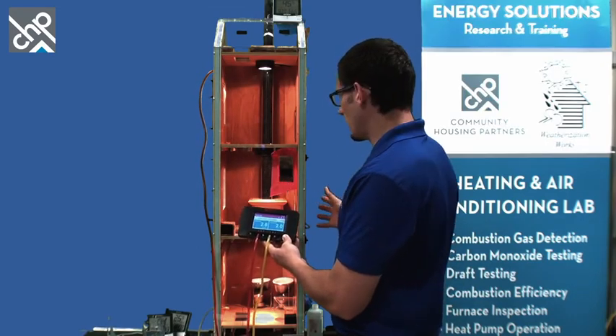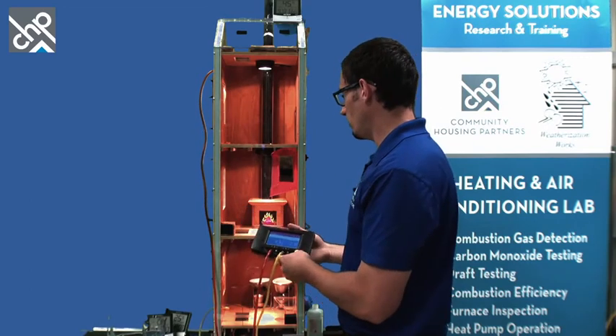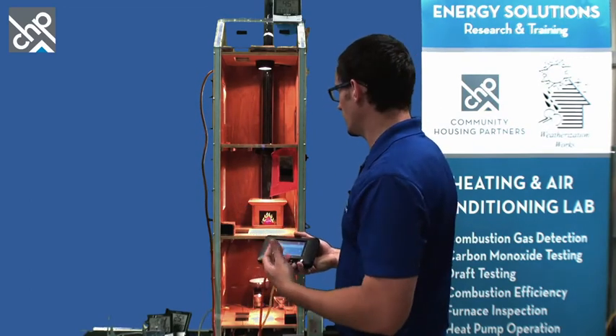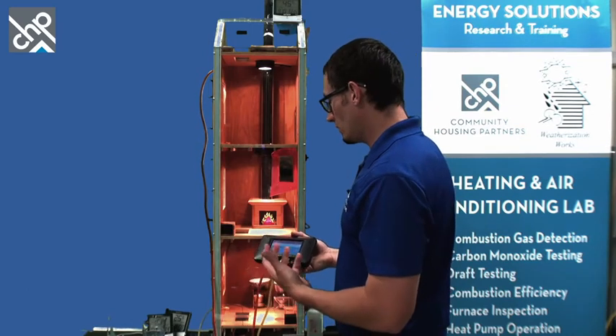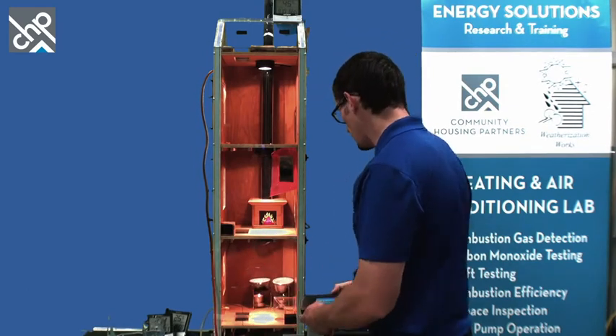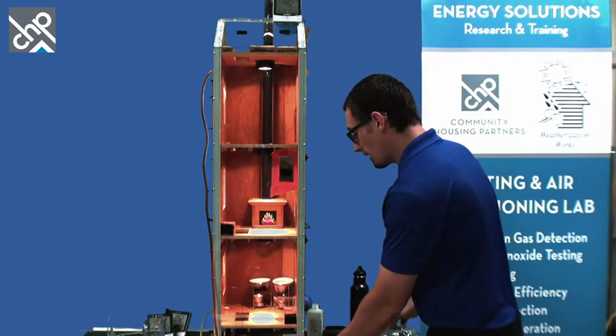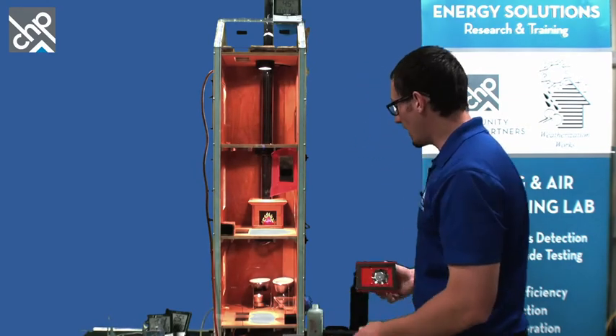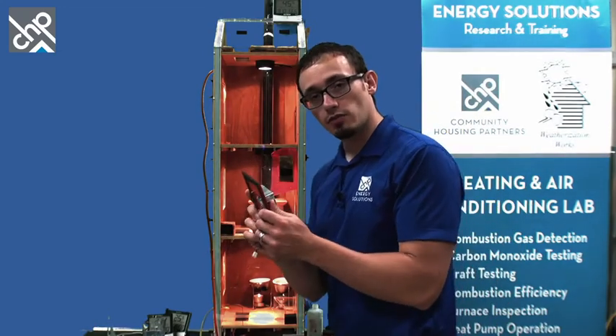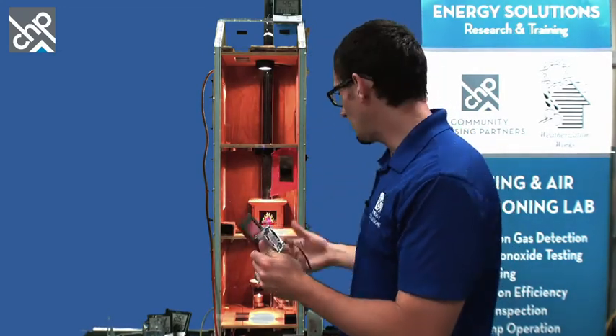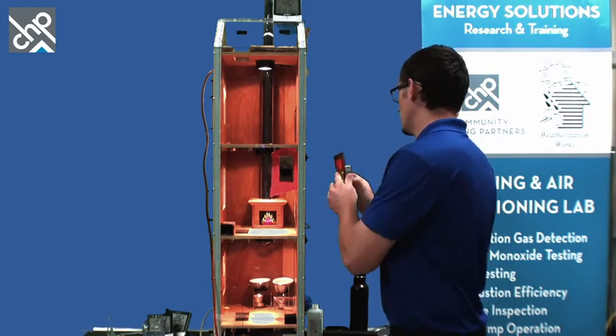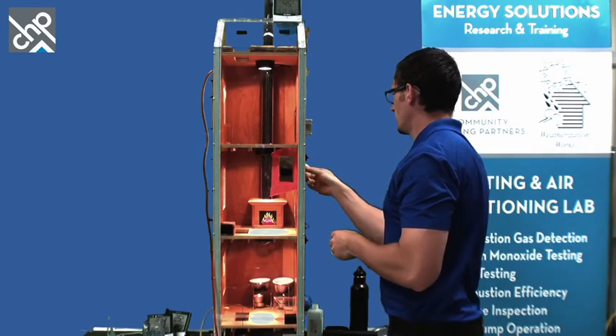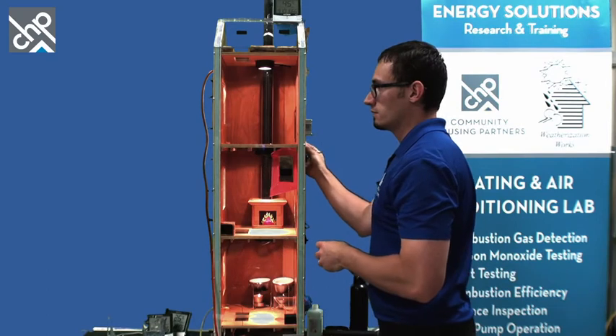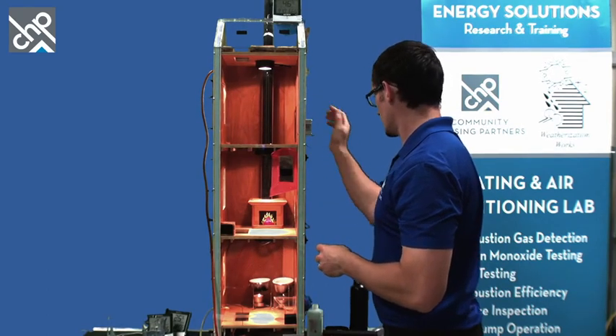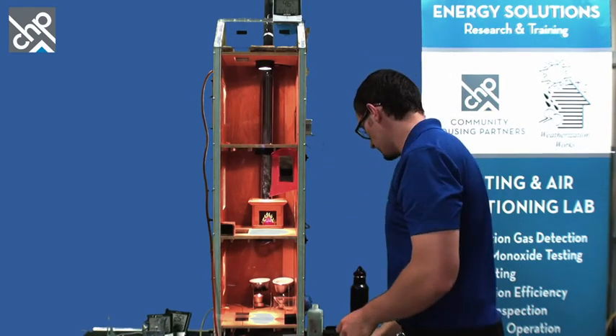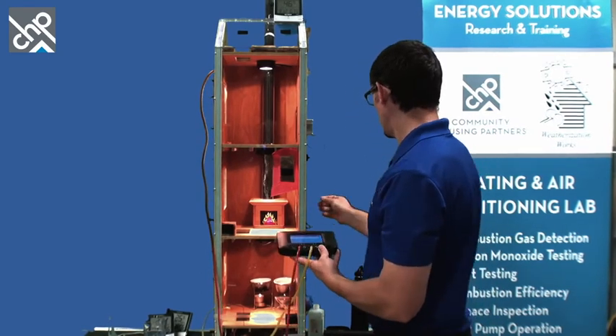So I can turn it around and I can do supply pressure, positively pressurize the building envelope. Or best case scenario, maybe I have two fans, or maybe I have an ERV, or maybe I have an HRV, some sort of balanced recovery. So I'm going to add another fan, exhaust fan to complement my other one here. So let's turn this on. Now I've got one fan exhausting, one fan blowing air in.